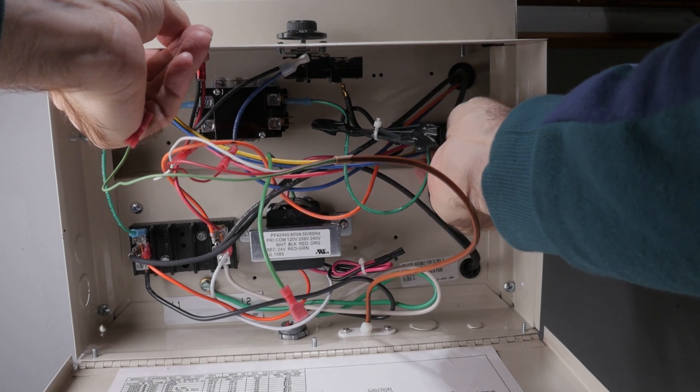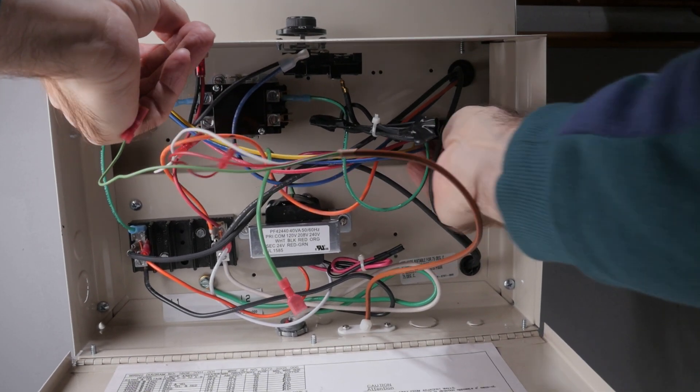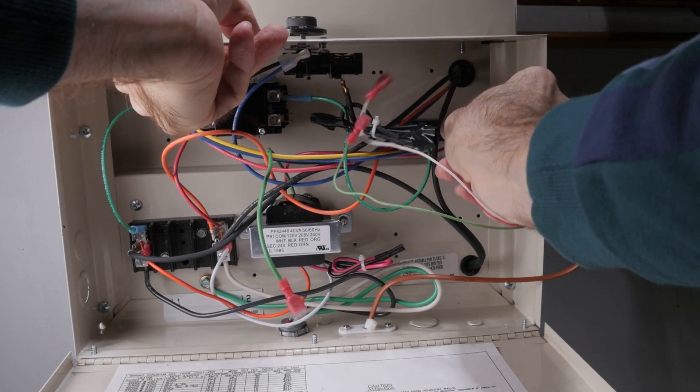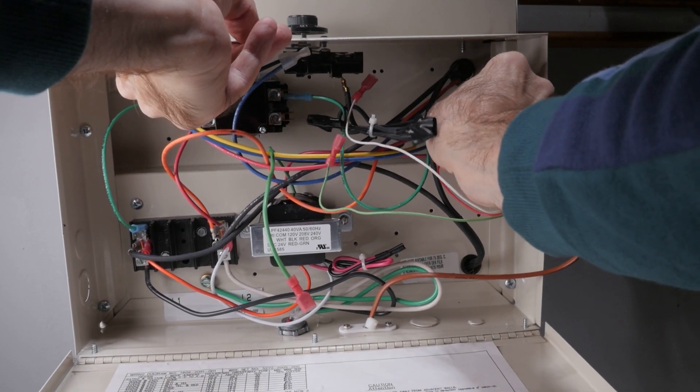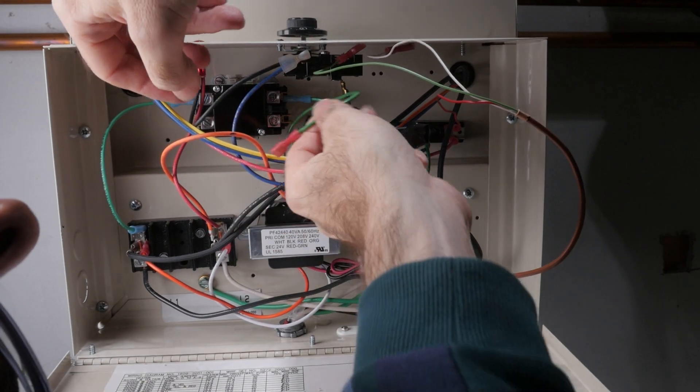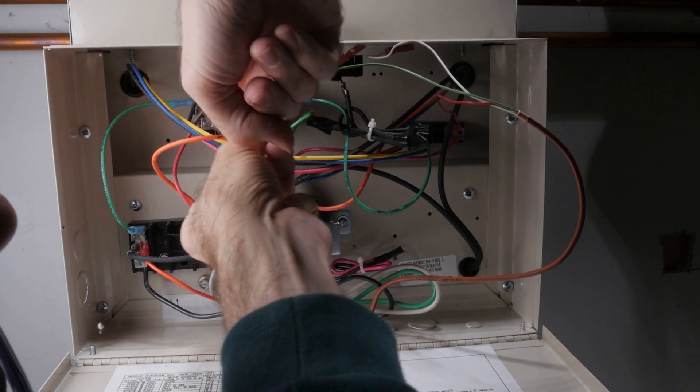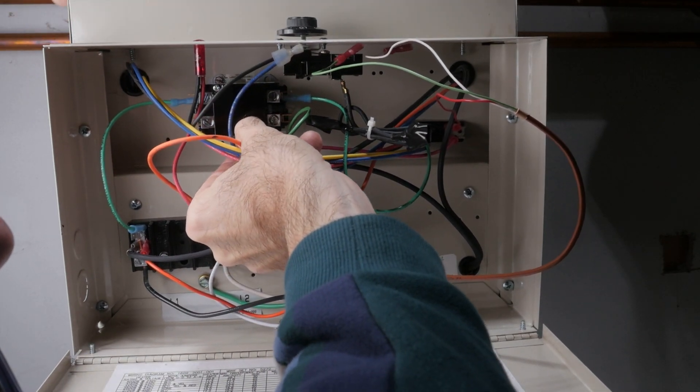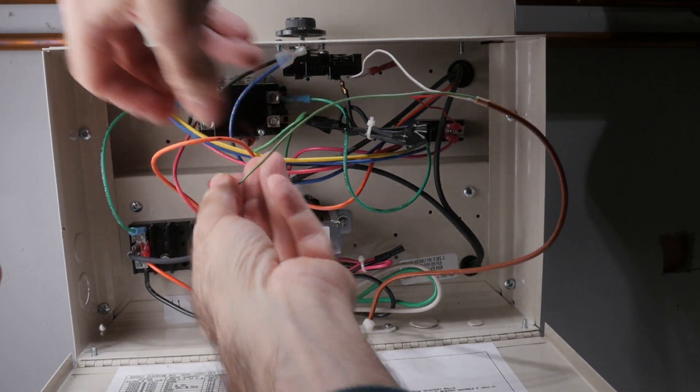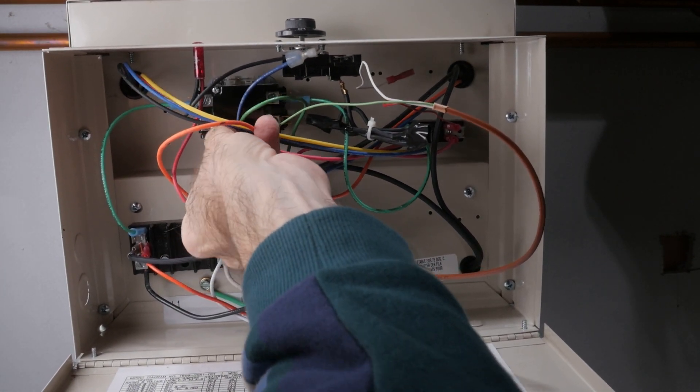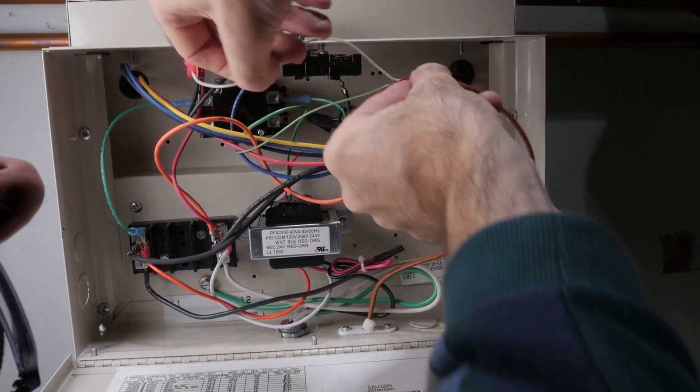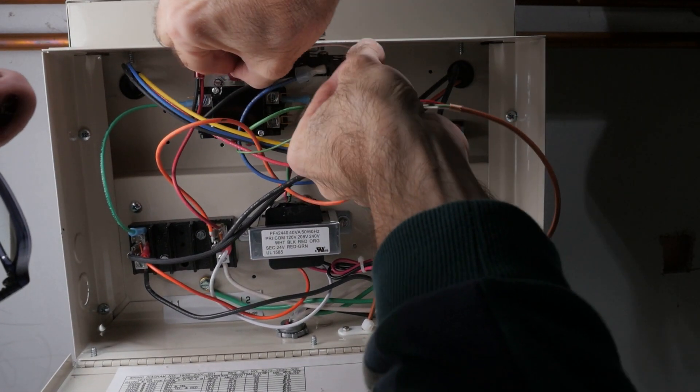Conveniently, there was a spare unused mounting lug and I used it to connect the red 24V secondary lead from the transformer and the red R lead from the thermostat together. The green 24V transformer secondary lead is next connected to one side of the coil on the contactor. The green C lead from the thermostat is connected to that same side of the coil, effectively connecting the two leads together. Finally, the white W lead from the thermostat is connected to the other side of the contactor coil.